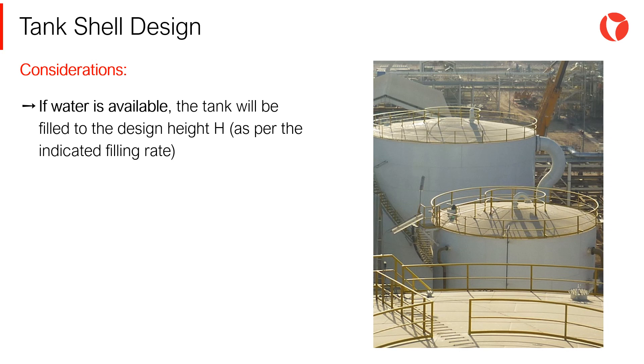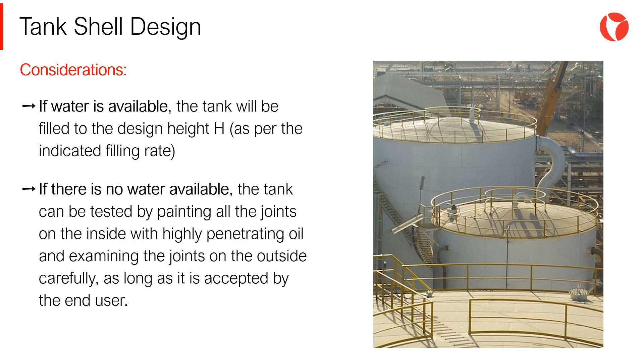If water is available, the tank will be filled to the design height. If there is no water available, the tank can be tested by painting all the joints on the inside with highly penetrating oil and examining them on the outside carefully, as long as this procedure is accepted by the end user.